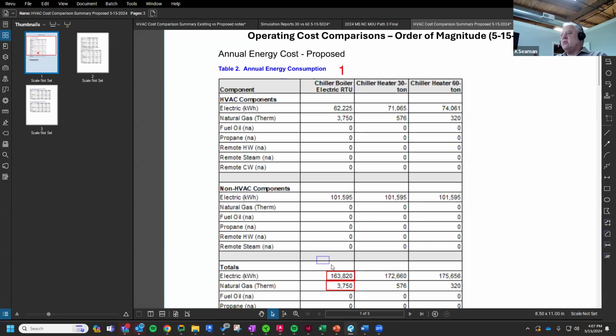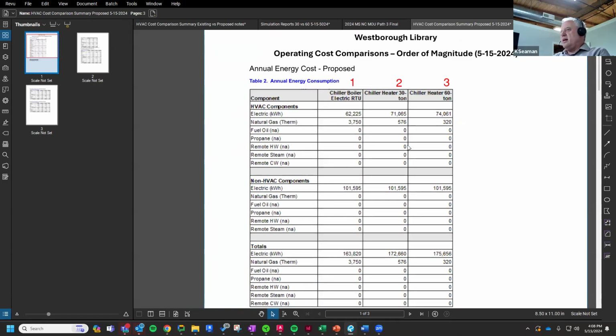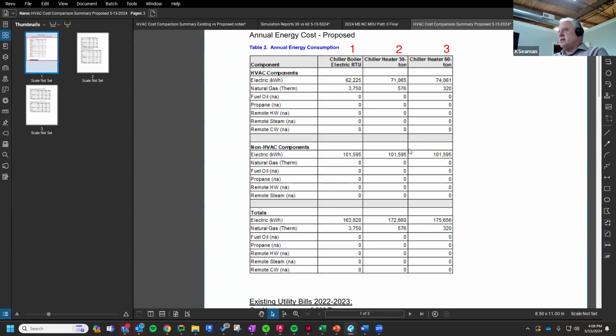And then the next two, options 2 and 3, columns over, would be if you were really trying to push the electrification further down the road, trying to really get this building to be more electrified. Again, in the model, this chiller heater is like a heat recovery chiller. The closest thing I can model it to is a VRF, so I've tried to layer in VRF. There are certain caveats in here, like the pump energy isn't fully picked up on options 2 and 3. My guesstimate is that would be another $600 on each one of those for options 2 and 3 in electric consumption to pick up the pump. So they would show a little more power. I think I noted it on another slide, but we can stay on this for now.